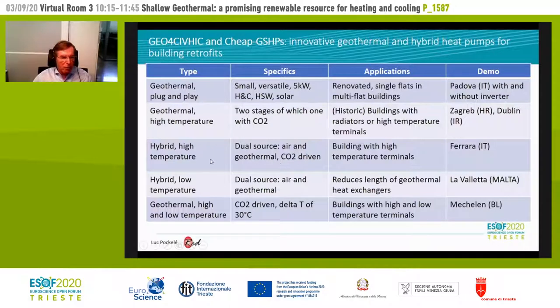In another project, a dual source heat pump was developed, and we are using it in 2 applications. One is the high temperature one, where in a historical building in Ferrara, we will demonstrate connecting it to high temperature terminals. It is a dual source, meaning we supply energy from the air and from geothermal. In the case of cooling, these 2 sources are used in series to create a sufficiently high delta T to reach good performance with this technology, because a CO2-driven heat pump needs a high delta T, which we create by putting air and geothermal sources in series in Ferrara. We also have a low and medium temperature application with that dual source.